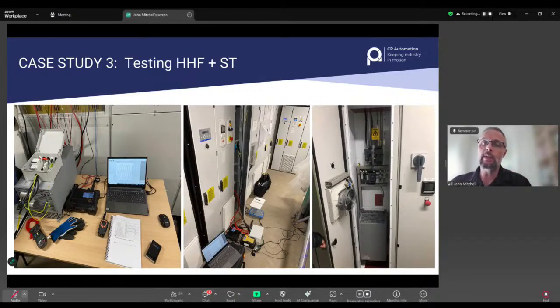But the main problems we were there to fix were transformers having gas bubbles and gases in the oil results, which meant the transformer's warranty was being invalidated. In addition, the ABB drives, which are active front-end drives, were causing problems with the generators.